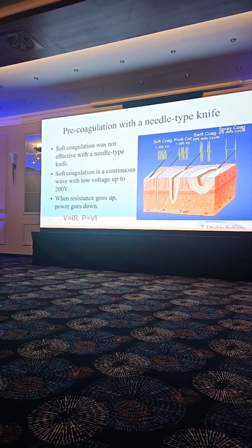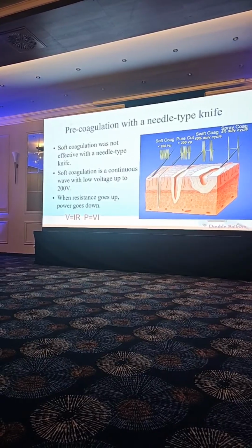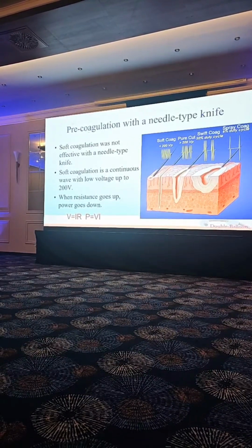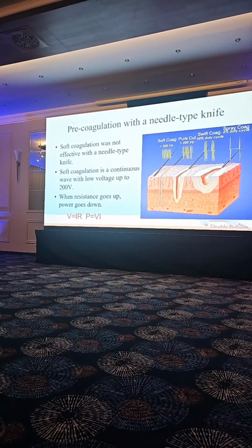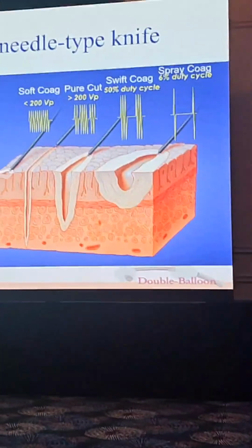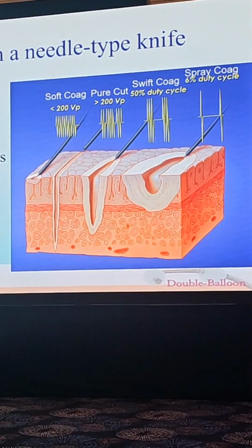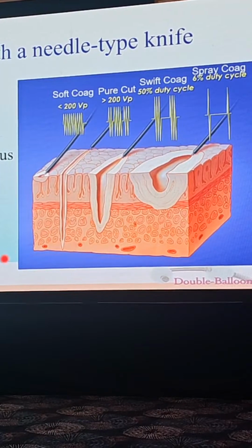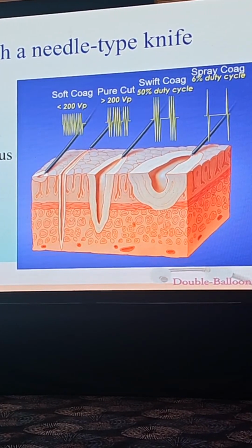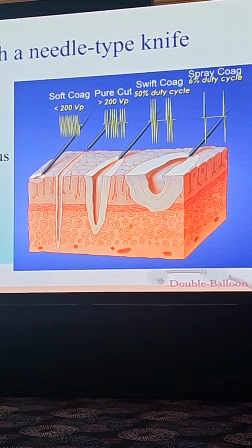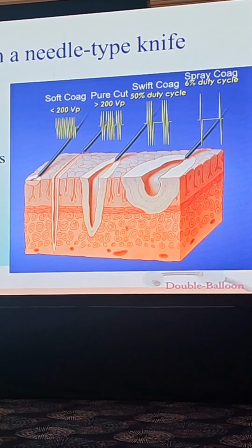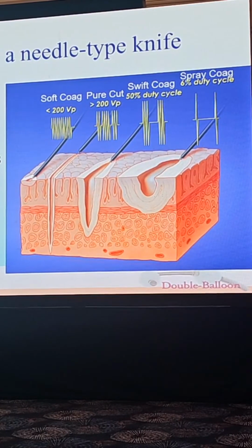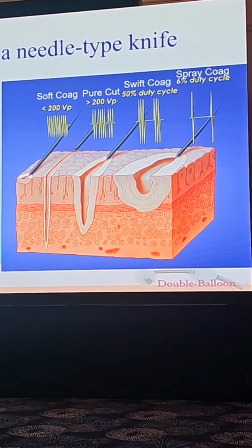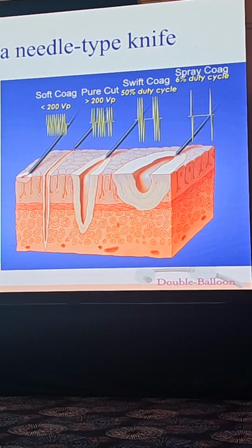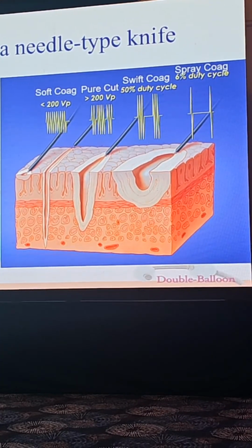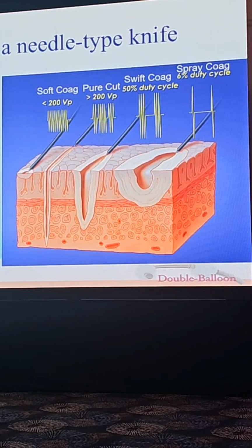Because the contacting surface of the knife was too small. So just try to coagulate the blood vessel with the knife, and just the tissue around the knife is coagulated, then the resistance goes up. Voltage is limited to 200. Then, if the resistance goes up, no current flows. So it doesn't work. So that was the reason why I was not using the soft coagulation with the knife.